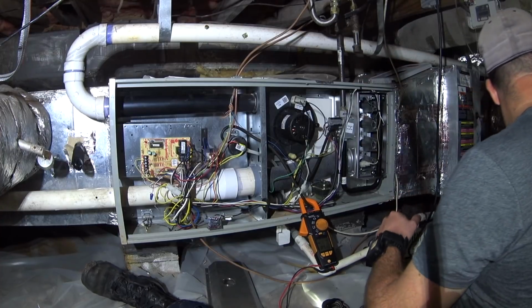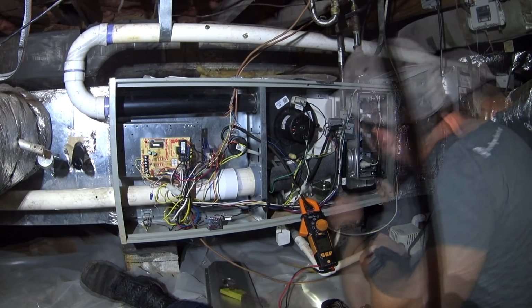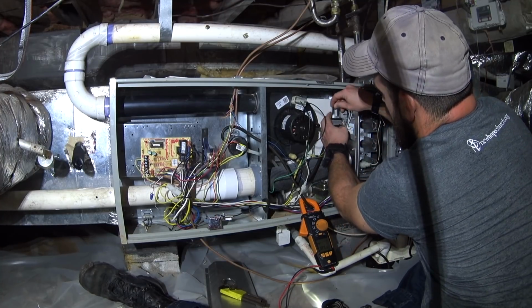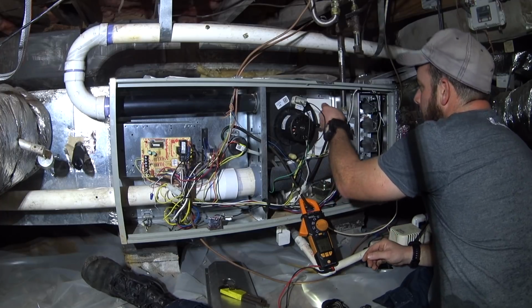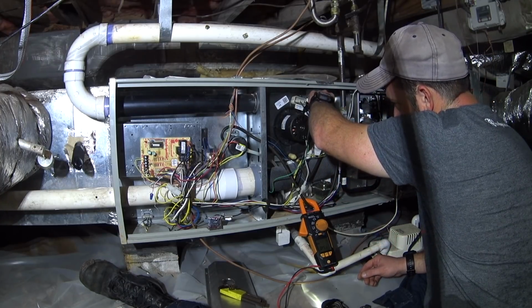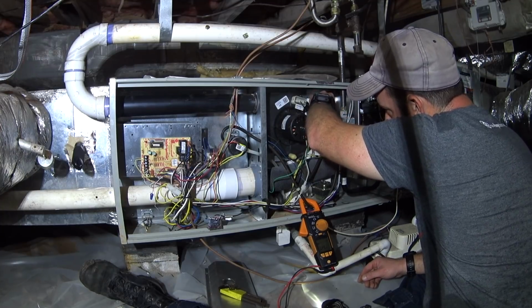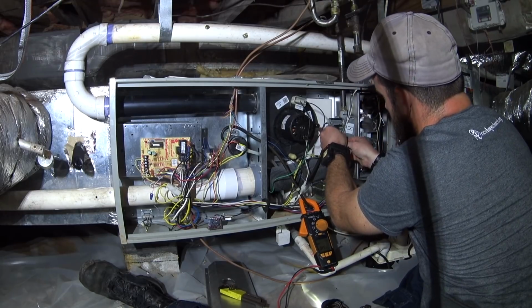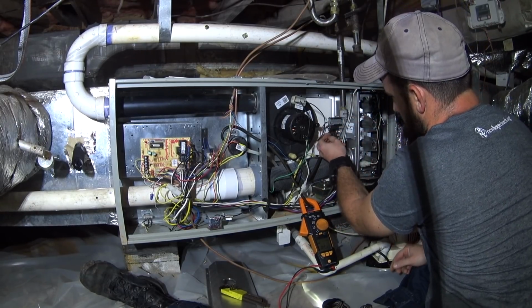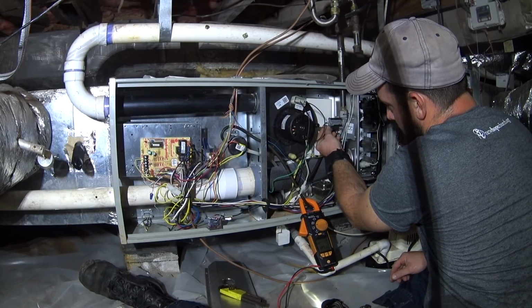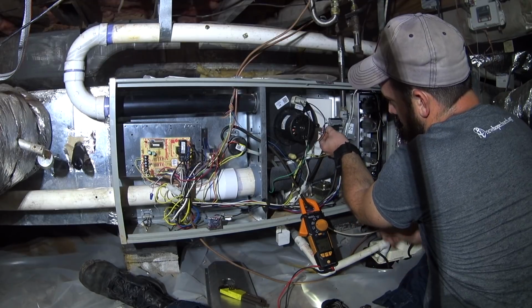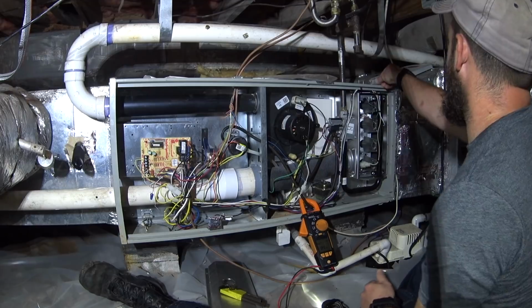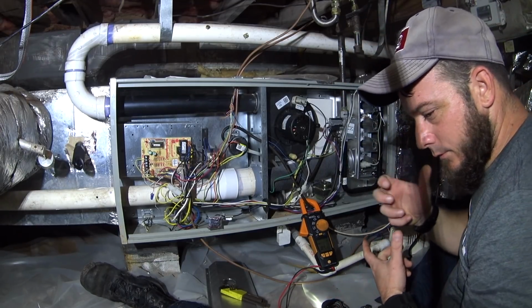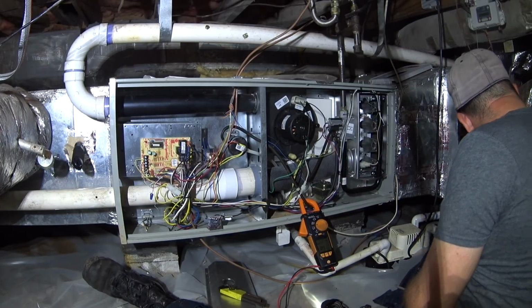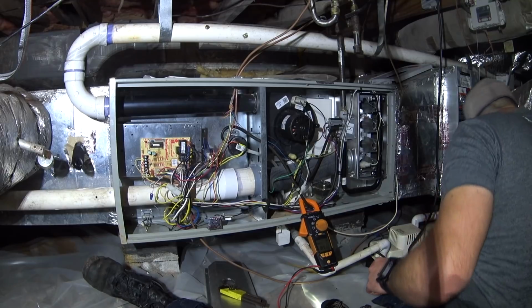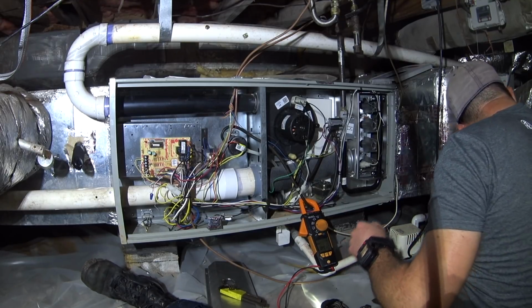Let's shut the gas off and get ready to take gas pressure here with the gas valve. I'm trying to remember what, I think it's a White-Rodgers gas valve. You don't have to remove the screw completely. You can loosen it a few turns and generally get the manometer to take a reading of the gas pressure by just loosening it. They have the smaller, I don't know, 1/8 inch screws rather than the large plugs that you would use your service wrench to remove. They can be very easy to lose, and you don't want to lose them. So you can just back them out a little bit.